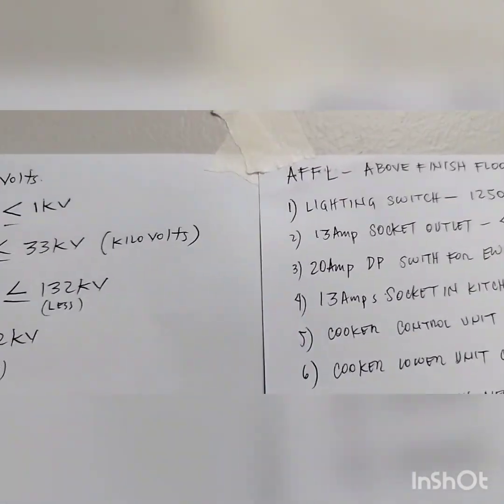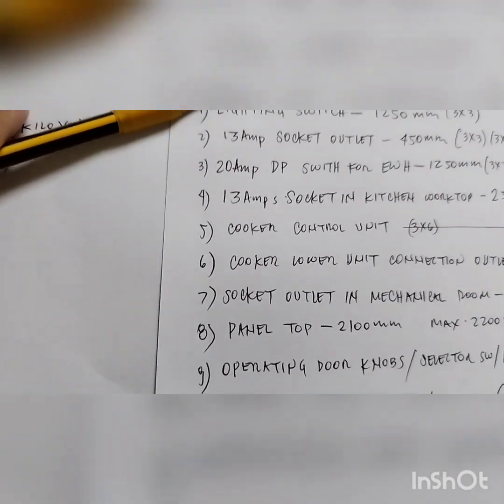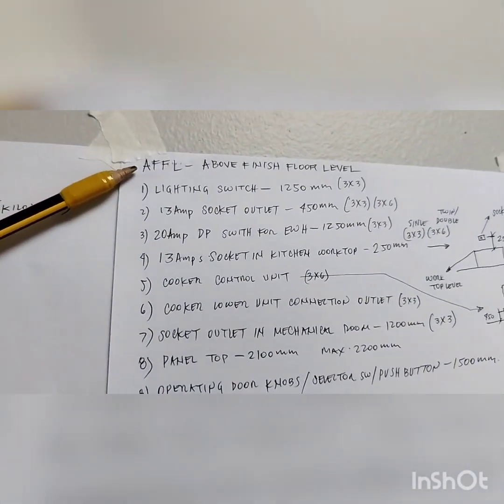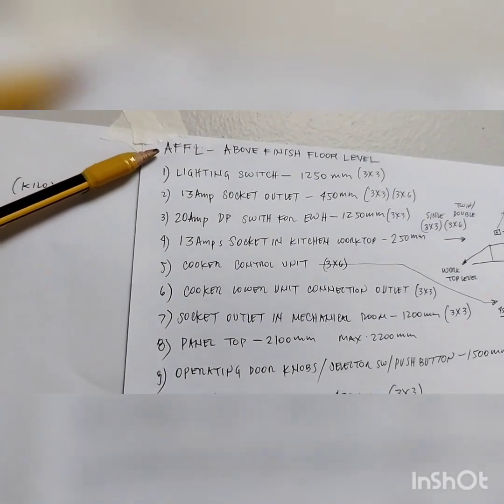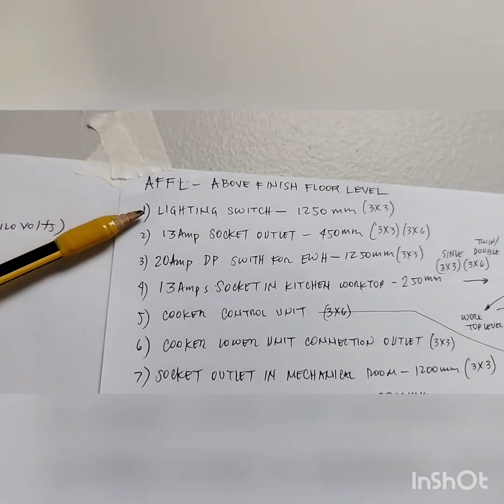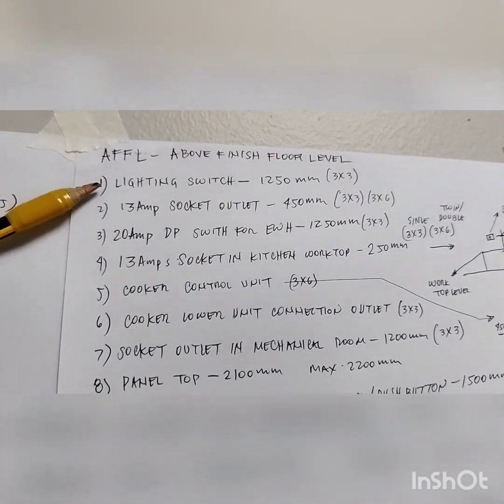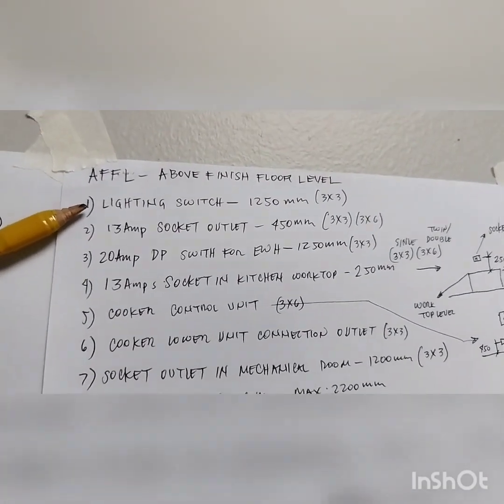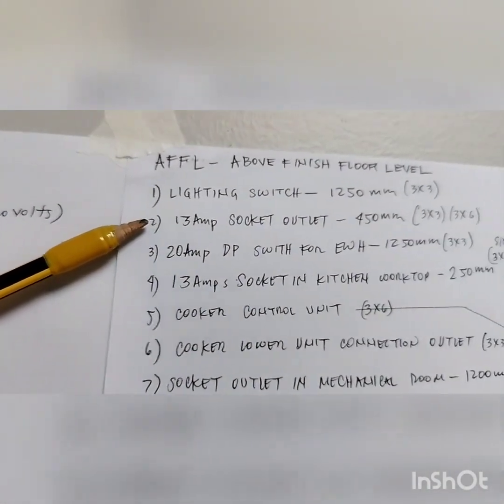Our next topic is about mounting height. When dealing with mounting height we always use AFFL, which means Above Finished Floor Level. Your measurement always starts from the finished floor level upward. For the lighting switch, the standard mounting height especially here in Qatar — and as I said it depends on the project specification — is 1250 mm from the center of the box. Normally we use a 3x3 GI box.